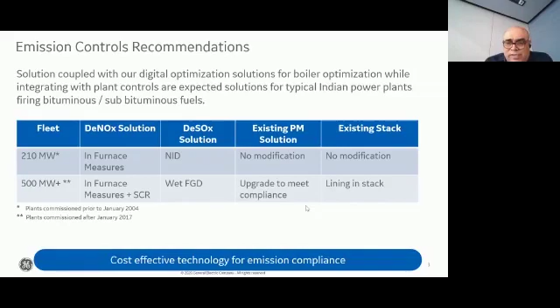When it comes to the NOx solutions, we see that for most of the plants, we are able to bring down the emissions well within the norm. It was 300 earlier for the plants up to 2016, but now the emission norms have changed, and we can go in with 450 also, I believe. And I think I've seen the notification for that as well. And these can be achieved by primary measures itself, that is going in for low NOx burners, or over fire air, or SOFA, which we call it. And with these, we will be able to achieve the primary NOx emissions well within the norms. And if we need to really go in the range of 100 milligrams or lower, then definitely we need to go in for SCRs as well.